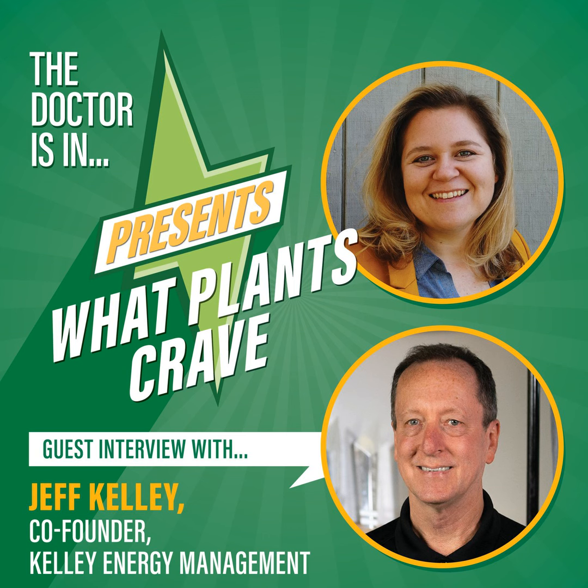in the building and not really thinking about part loads or the dynamic loads within the building and how that might affect energy use. That's correct. Yeah. What I found is that the engineers will add up the BTUs of the lights and come up with a sensible cooling load from that and do something with the evapotranspiration and all the latent load. And then they'll size their equipment.